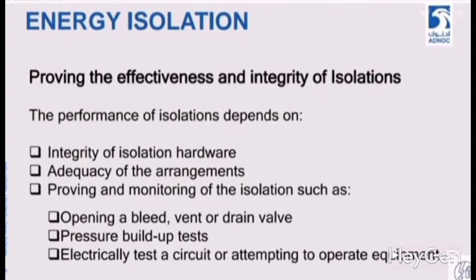The next point is proving and monitoring of isolation. When we have done isolation, how do we test it? So the first point we have is opening of the bleed vent or drain valve. If we have a drain valve ahead of isolation, we can simply open it and do pressure testing from there to see if any material is coming, if any supply is running, whether it is properly isolated or not.